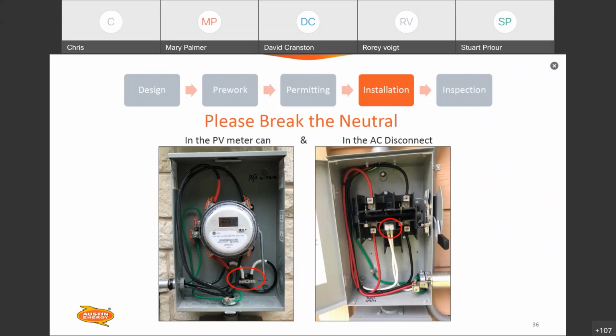Okay, so the neutral needs to be broken in both the meter can and the AC PV disconnect. You can see here in the meter can, you've got an isolated neutral bar, and you've got a Polaris block in the disconnect. And the reason for that is the utility may need to access that neutral for testing in the future. So please break the neutral in one of those two manners right there, so that, like I said, AE can have access to that neutral in those enclosures if necessary.